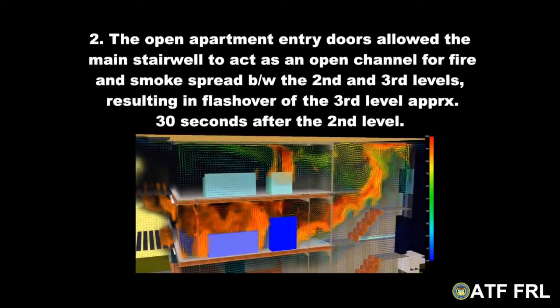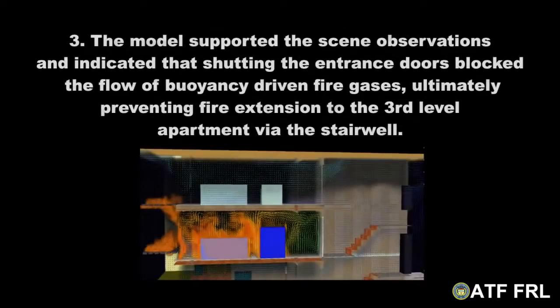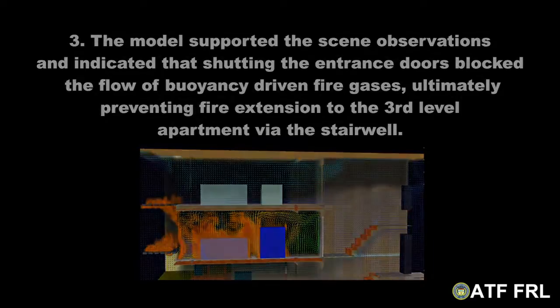Conclusion 2. The open apartment entry doors allowed the main stairwell to act as an open channel for fire and smoke spread between the second and third levels, resulting in flashover of the third level approximately 30 seconds after the second level. Conclusion 3. The model supported the scene observations and indicated that shutting the apartment entrance doors blocked the flow of buoyancy-driven fire gases, ultimately preventing fire extension to the third level apartment via the stairwell.